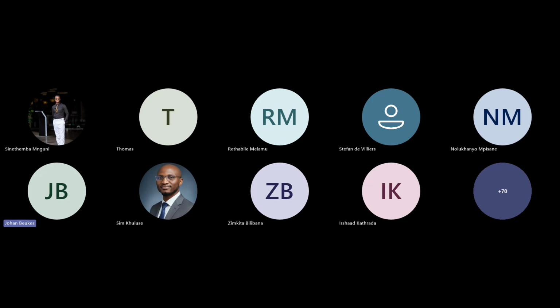What will happen, I think, is if it goes below 5, you will specify that the technology you install must be grid forming. So from a network perspective, we want the BESS systems to support the grid, we just need to do it in the right way. We will typically say below 5 you go for grid forming, above 5 you go for grid following, because grid forming above 5 means you're connecting very strong voltage sources together, which can create other issues. So that will typically be the specification, something like that, eventually.